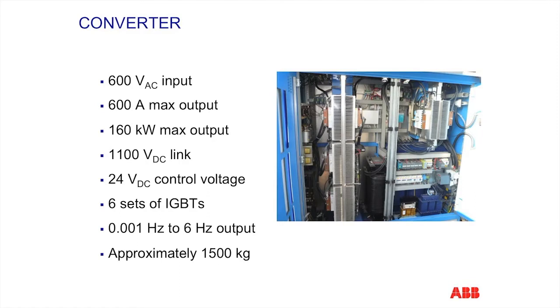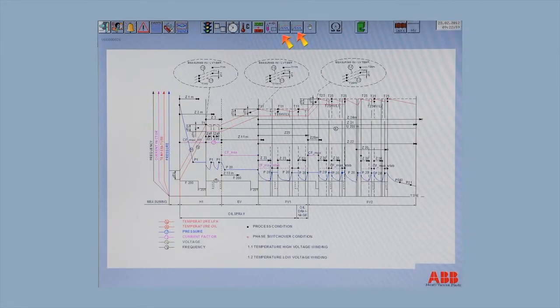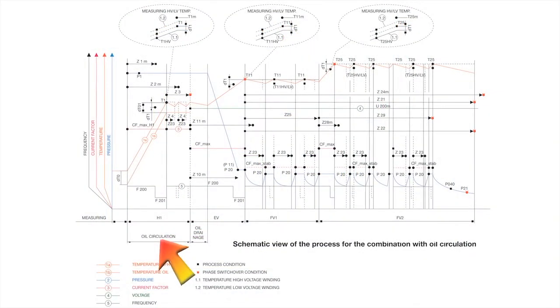The DC link and the IGBT switch properties show what the LFH is capable of doing. The LFH cycle. There are 2 LFH cycles that can be selected from the menu bar. One LFH process involves an empty transformer where heated oil is sprayed into the transformer and recirculated. The oil heats part of the insulation that may not be in direct contact with the windings. The second process involves a transformer that is filled with oil for the initial heating steps of the process, but which is removed in the evaporation stage.